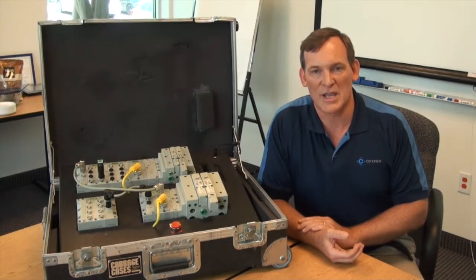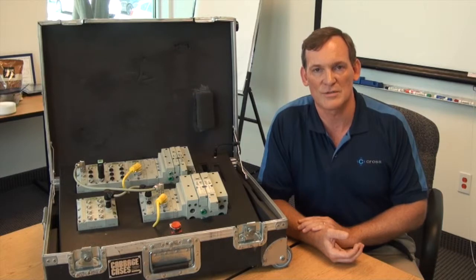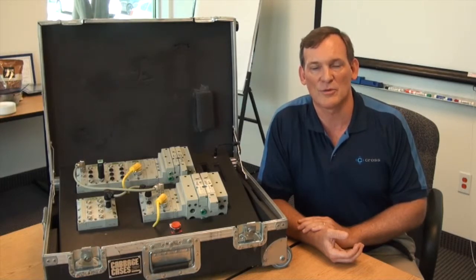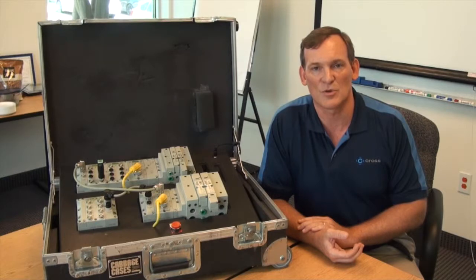This device especially comes in handy for the OEM who needs to commission nodes for similar machines. The MCM can be connected to a manifold and once power is cycled, the user can opt to have the MCM write parameters to the node. Once this is done, the MCM can be removed from the manifold and is ready to be used on a similar manifold on a different machine.